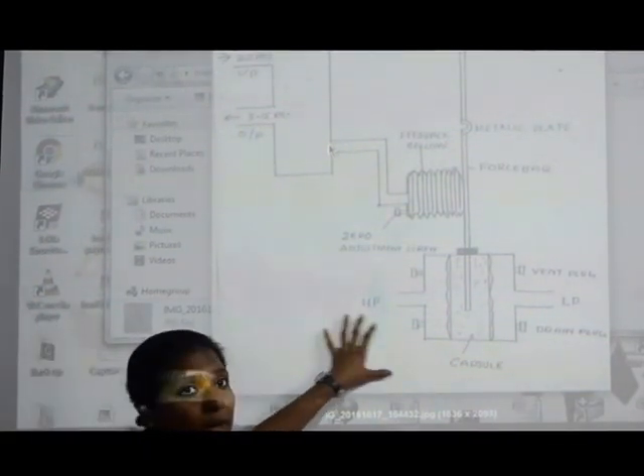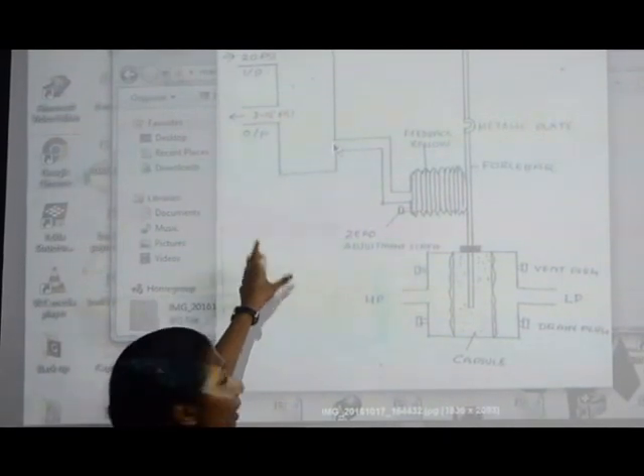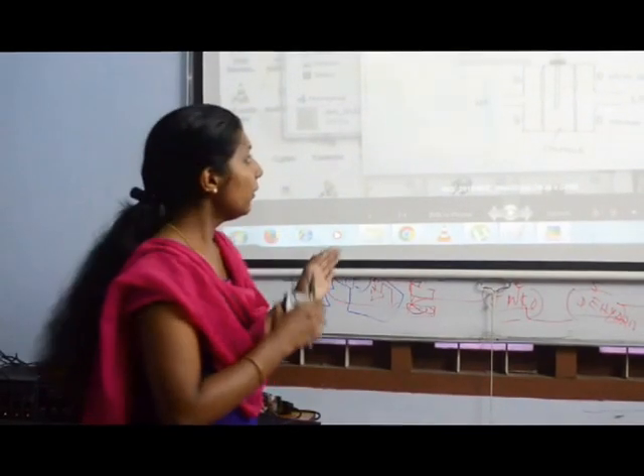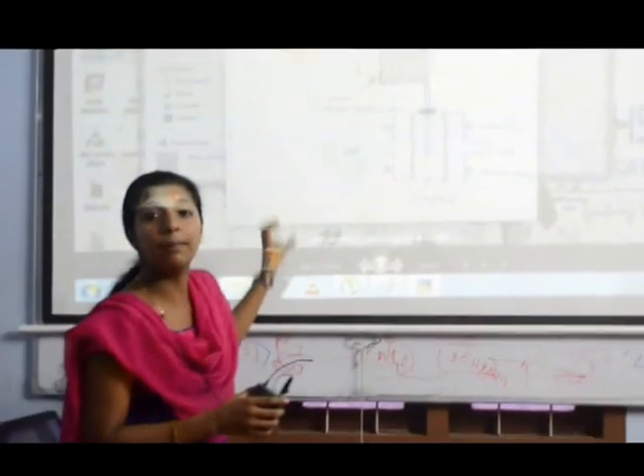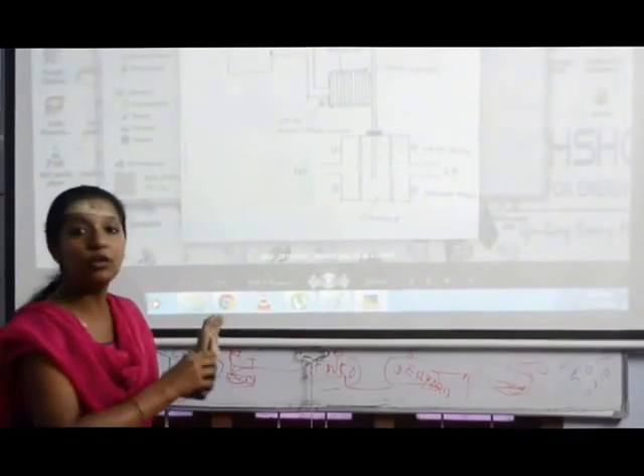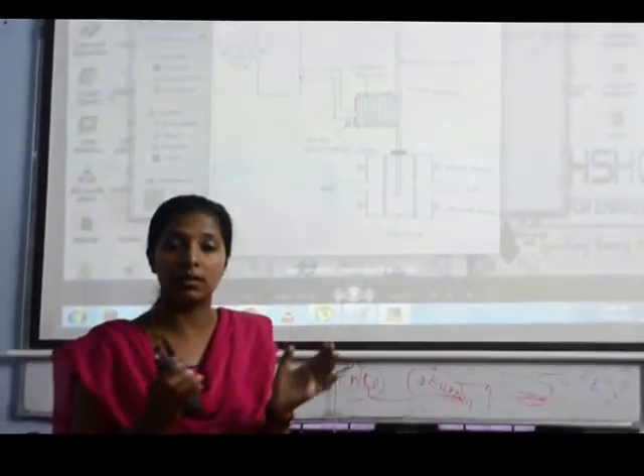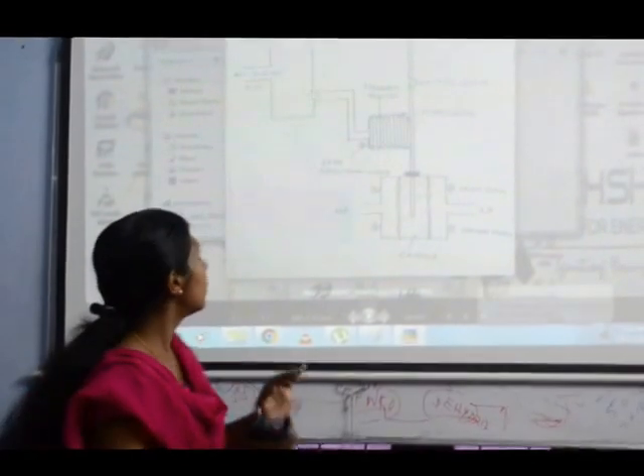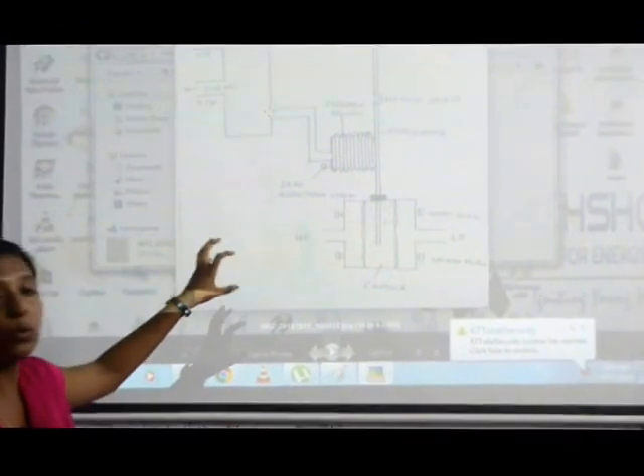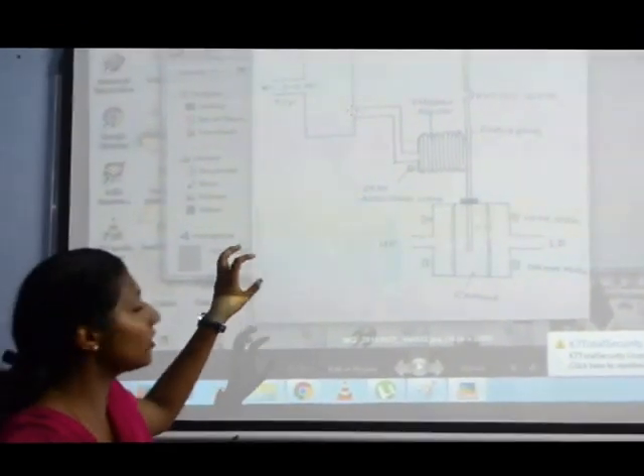Here we are giving a 0 to 100% output from the sensor section, and we are taking the output in a 3 to 15 psi manner. We are giving the minimum to maximum sensor output and taking a proportional 3 to 15 psi conditioned signal. This signal is able to be understood by the controller. This is what is actually happening inside a pneumatic transmitter.